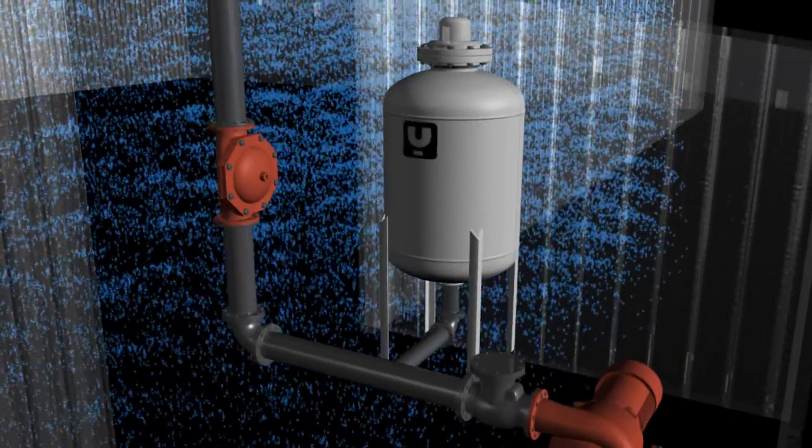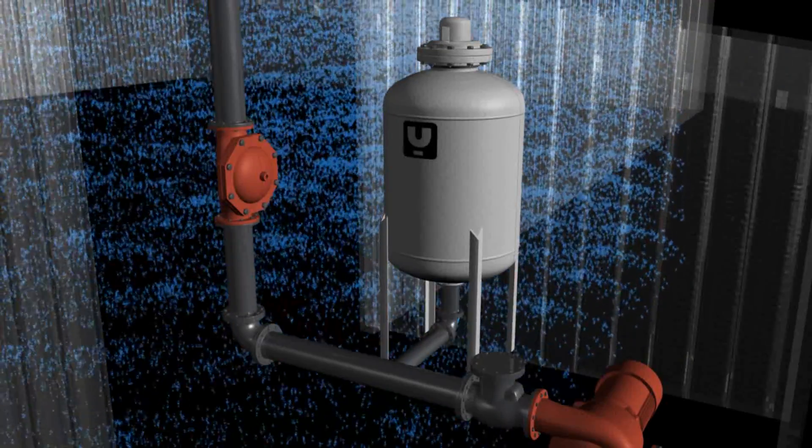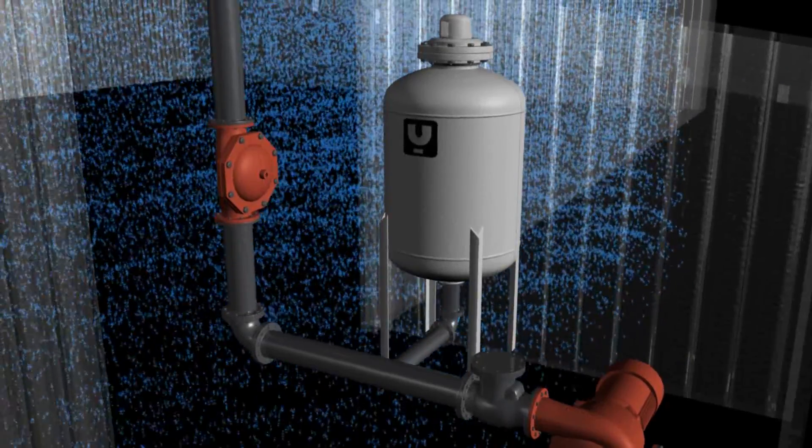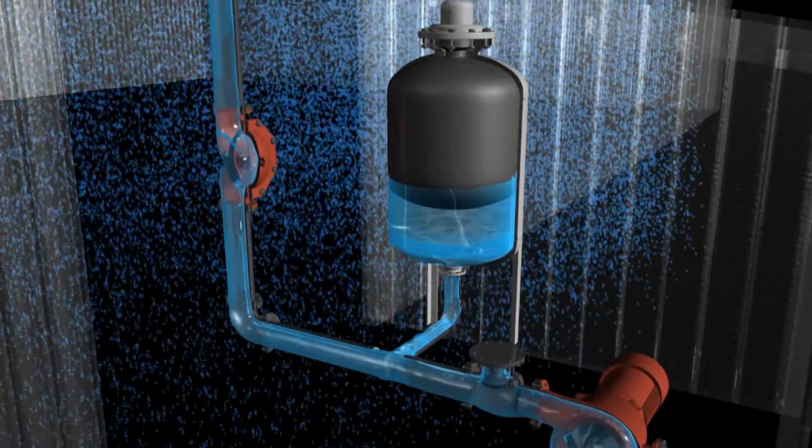After the deluge valve opens, a bladder surge tank is located in the system to provide water into the pipeline, preventing a column separation.